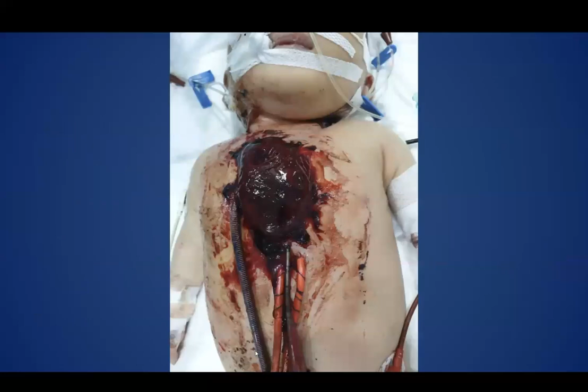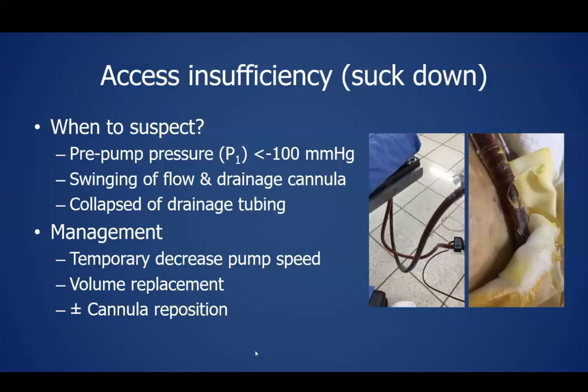Whenever you see chattering of the venous line, suck down is suspected. The mechanism is that the vessel or atrial wall is sucked against the drainage holes of the cannula and blocks the blood flow. To address the problem, the pump speed is temporarily reduced to free up the holes, followed by giving volume or adjusting the cannula depth before increasing the RPM back to the targeted flow.